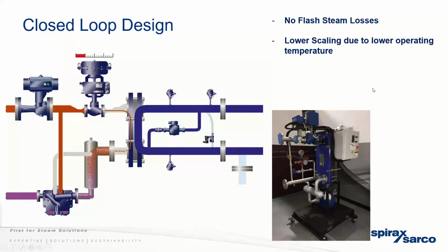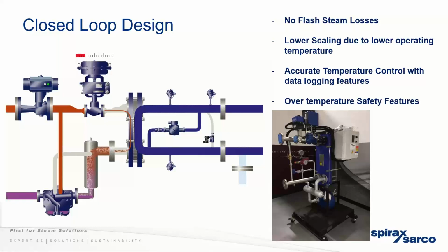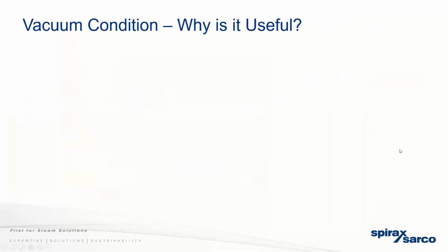So the system is sized for no flash steam losses. We designed the system to operate in vacuum. The pump trap will take care of the condensate. Because it operates at low temperatures, there's going to be low scaling within the heat exchanger. So we could have, well, I'll show you in a few slides, high pressure steam going in, but it's still coming out under vacuum. So accurate temperature control and data logging features. If it's a requirement for the facility to log their sanitation temperature, there's that option in the control panel to data log and make sure for your HACCP program that you have accurate temperature for proper sanitation. And I've mentioned a few of the over temperature safety features.